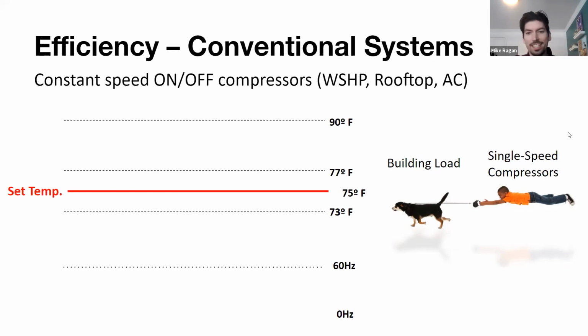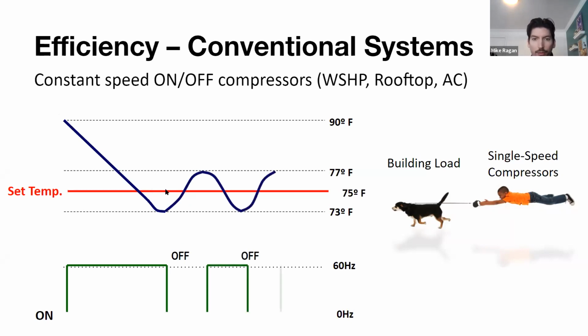I most liken this to, for anyone who's walked a dog before, if you are not quite in control of the situation, the dog is ultimately leading you on that walk. In this situation, we're allowing the temperature of the space to guide what the system is doing, as opposed to the system guiding the temperature of the space. In this particular example, we have a compressor that is turned on in order for the indoor space, which starts at 90 degrees, to start to cool. We want to get that 90 degrees down to the set point of 75 degrees. So the compressor will come on and lower the temperature within the space, and as soon as it overshoots, it's aiming for 75 degrees.